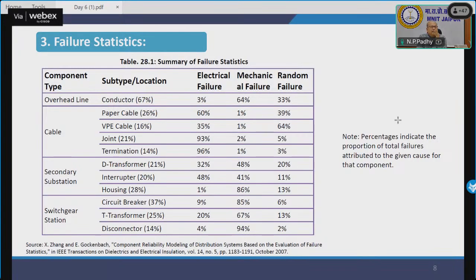Now similarly cables: paper cable, VPE cable, joint cable, termination cables. Out of which you could see there is one thing. For example, paper cable: 60% of failures are related to electrical and there is no mechanical failure. Then why do I waste my time focusing on mechanical failure of paper cable, whether it is strong, whether it has strength? It is a waste of time in maintaining it. So this is how it works for each and every secondary substation.